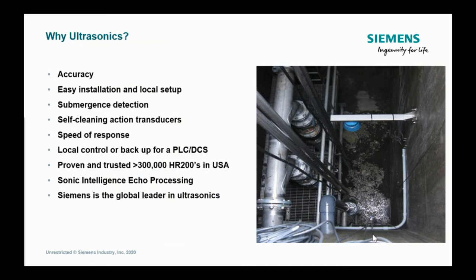Okay, now, if you've got a lift station like we have pictured here, and you come up to 10 feet, turn the pump on, go down to 2 feet, turn the pump off, if you're plus or minus a couple inches, who cares? Close enough, right? Accuracy isn't really super important in that application. Up in Idaho recently, we were looking at an open channel flow. It was a 6 foot wide rectangular weir. A quarter inch of difference in measurement made a difference of 250,000 gallons or 0.25 MGD that was overreported or underreported to the state DEQ. Okay, in that case, accuracy is the key driver there.